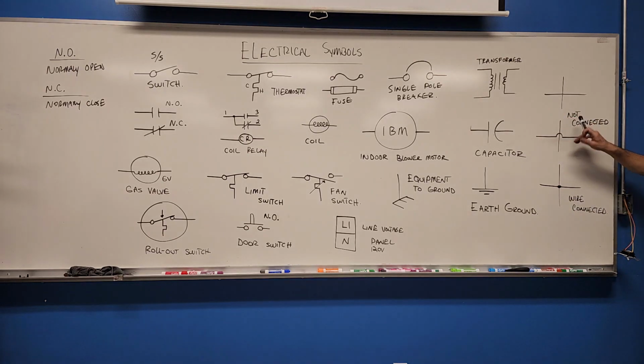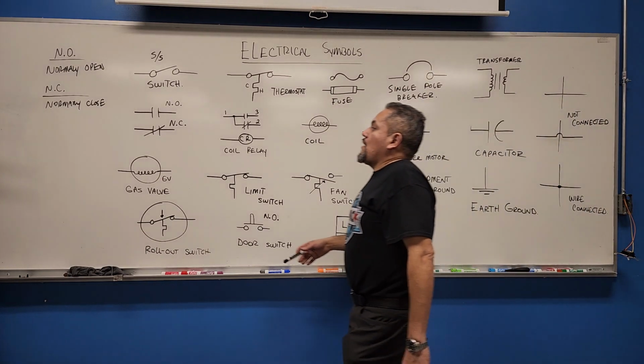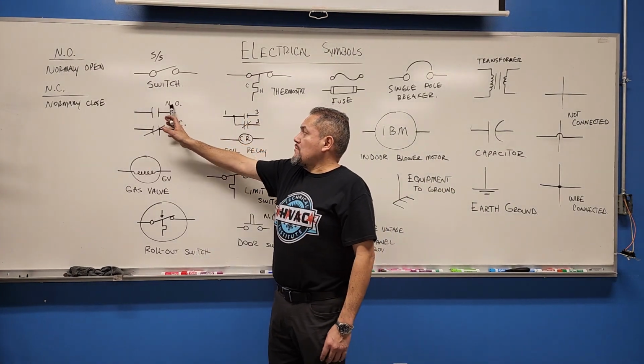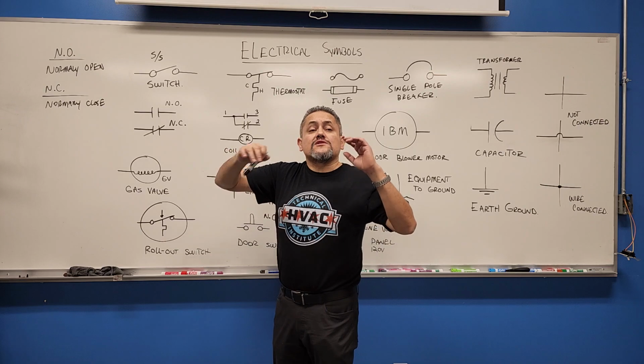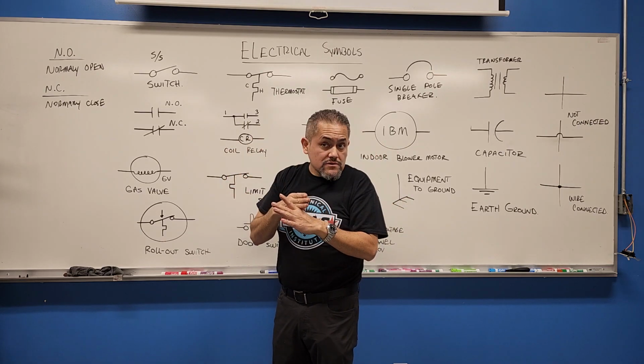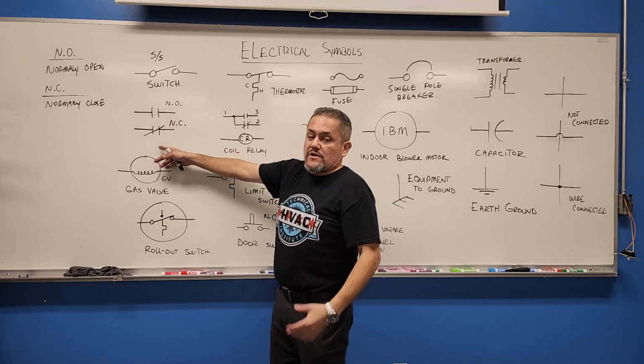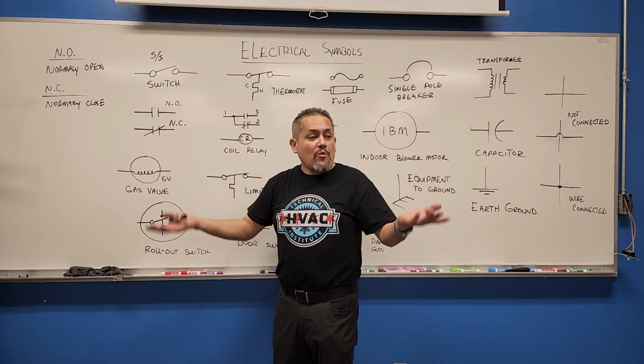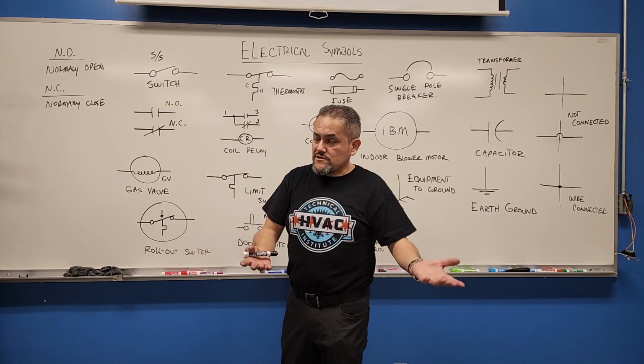And then we got the symbol for when we run wire diagrams and the wires cross, either it's going to be no contact, not connected. This one or this one should be not connected. And if there's something connected, it would be this symbol here. You know, when the wires cross, there's a dot right there in the middle, so that means it's connected. Alright? Now we go back all the way to the beginning here, and this is for the normally open contacts, which means there's going to be a point when this contact is going to close. But normally it's open. Or this one is normally closed, and there's going to be a point where it's going to open. So vice versa, okay? Depending on what the furnace is doing.